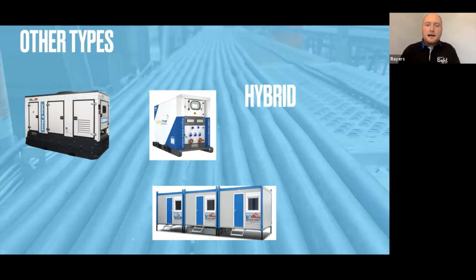Where hybrid units are perhaps more suited is in environments like site offices, where, much like I was saying at the festival example on a smaller scale, you might have a village of contractors at, say, a plumber's compound. They all come in at 6 o'clock, they all need a shower, want to get washed and dressed and changed, and they're all putting the heaters on. The demand there spikes right up. Then once they go out in the morning and go to work, consumption is virtually nothing - a couple of immersion heaters perhaps, but minimal.